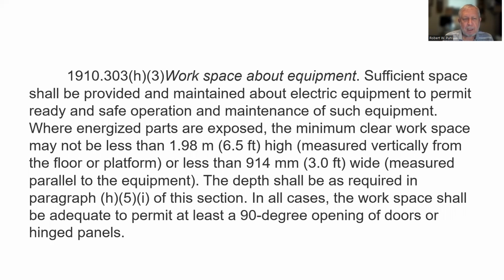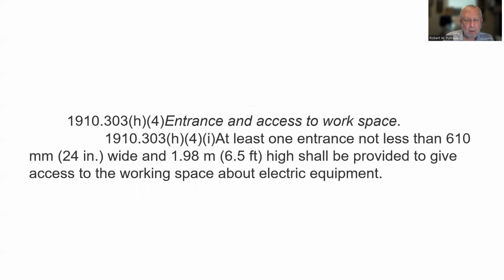Workspace about equipment. Sufficient space shall be provided and maintained about electrical equipment to permit ready and safe operation and maintenance of such equipment. Where energized parts are exposed, the minimum clear workspace may not be less than 6.5 feet high, measured vertically from the floor or platform, or less than 3 feet wide, measured parallel to the equipment. The depth shall be as required in paragraph H5I of this section. In all cases, the workspace shall be adequate to permit at least 90-degree opening of doors or hinged panels. That's a good idea too.